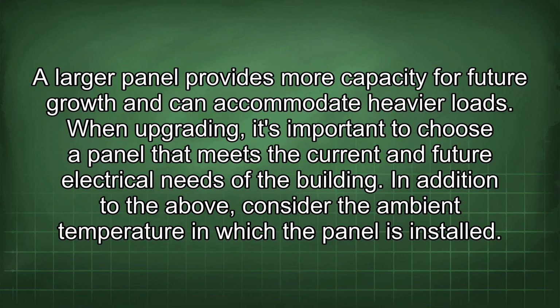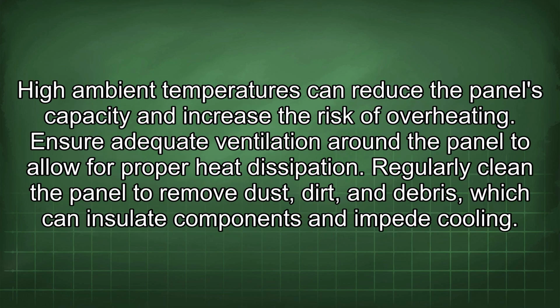In addition to the above, consider the ambient temperature in which the panel is installed. High ambient temperatures can reduce the panel's capacity and increase the risk of overheating. Ensure adequate ventilation around the panel to allow for proper heat dissipation.